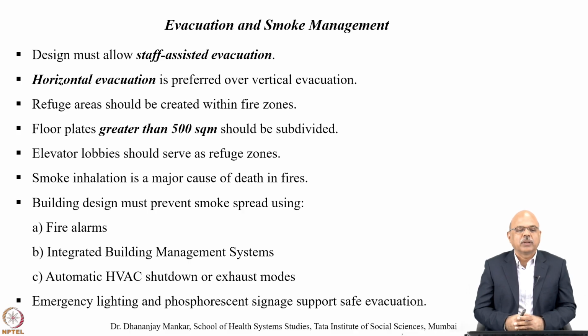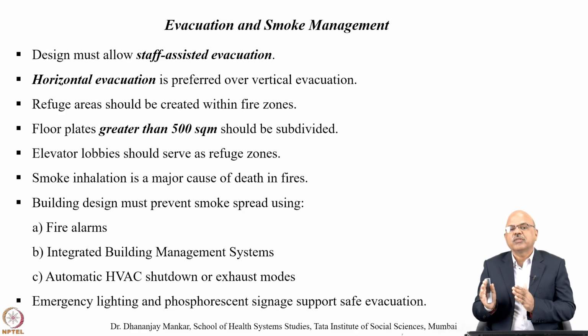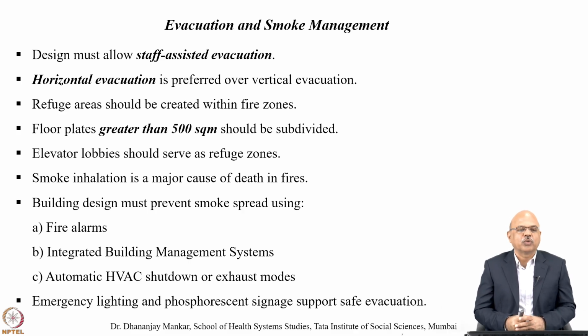Evacuation and smoke management. Design must allow staff-assisted evacuation. Horizontal evacuation is preferred over vertical evacuation, which is a very important part. A refuge area should be created within fire zones, which is essential while planning the institution. Floor plates greater than 500 square meters should be subdivided. Elevator lobbies should serve as refuge zones.